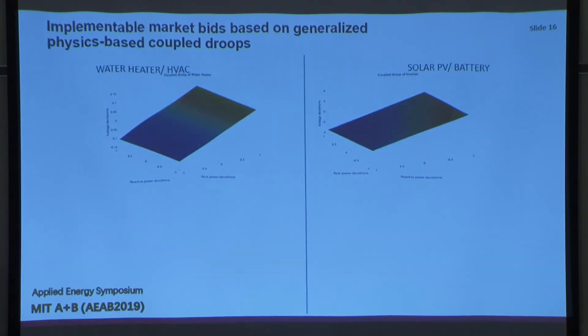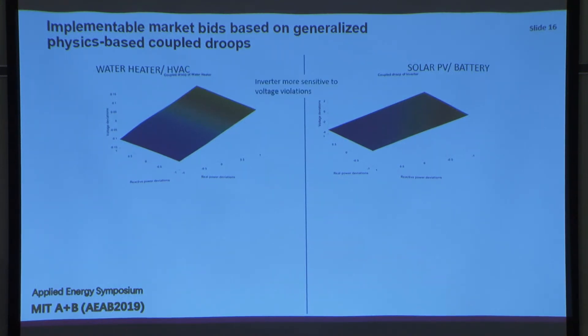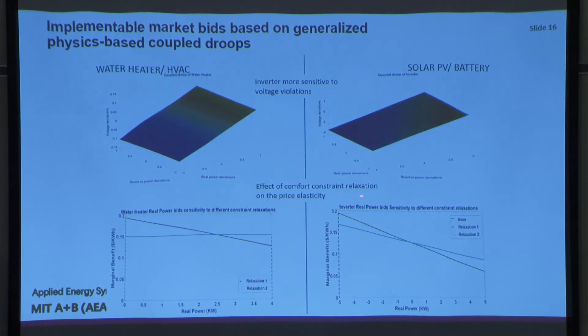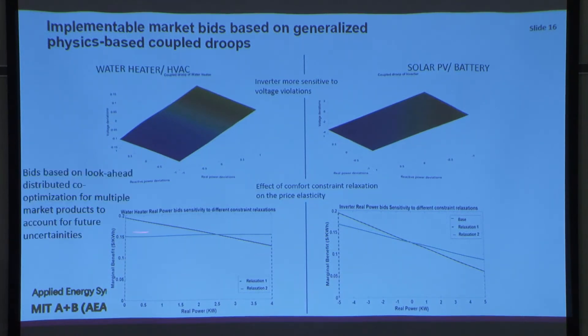Through embedded decision making at the device level, we found that water heaters and HVACs are less sensitive to voltage violations. On the axes of real and reactive power deviations versus voltage violation on the Z-axis, solar PV and batteries are more sensitive to voltage violations, but with small adjustments to real or reactive power set points they can control their own voltage. Device-level decision making also produces bids that depend on how comfort constraints are modeled — relaxed comfort constraints yield more flexible bids, while tighter constraints produce more horizontal bids. This bidding is based on look-ahead estimated market prices.